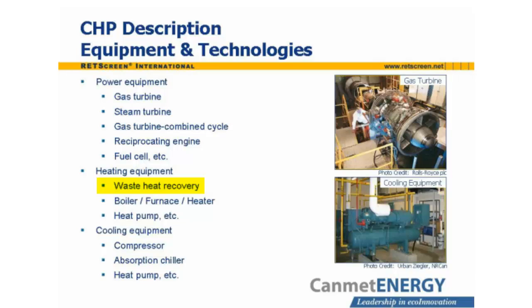A second essential component of CHP plants is the waste heat recovery unit, which collects the waste heat from the power plant so that it can be delivered to heat loads. The nature of the waste heat recovery system depends on the type of power plant, the required temperature, and the characteristics of the heat load. Most applications requiring high temperature heat will demand steam, which can be produced using the hot exhaust gases of a gas turbine or reciprocating engine, requiring a heat recovery steam generator. Steam turbines can sometimes provide low-grade steam at their exhaust port, or it can be bled from the turbine as necessary.